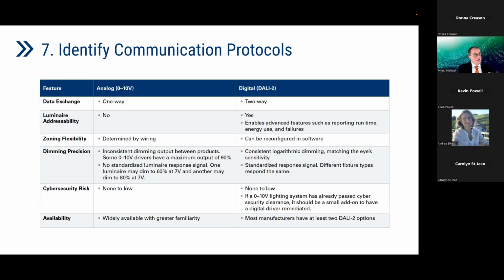Luminaire addressability is easier to get with a DALI 2 system; it's harder in a 0 to 10 system, requiring more complications with controllers. Your wiring plays a bigger role in 0 to 10, whereas with a digital system I can reconfigure things more easily. Dimming precision also differs between the two.